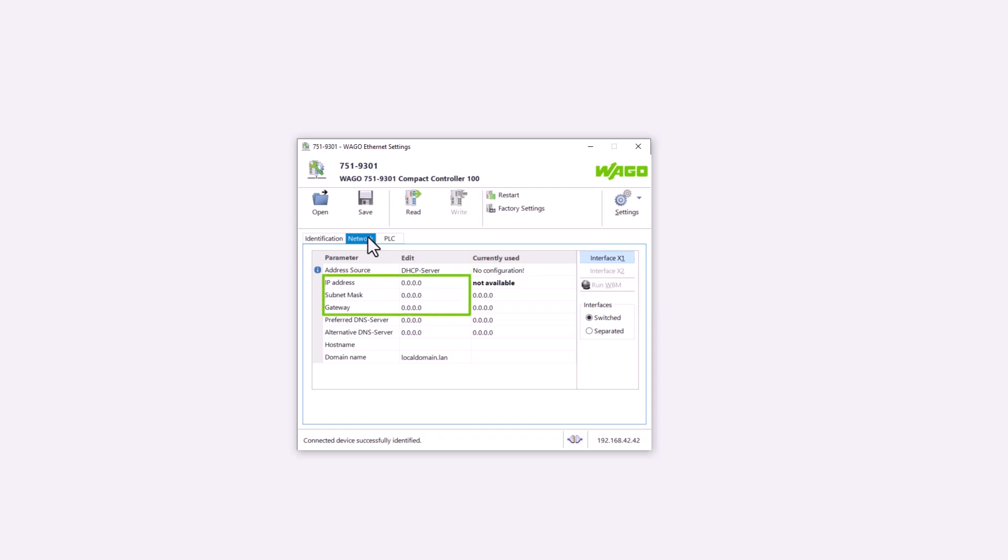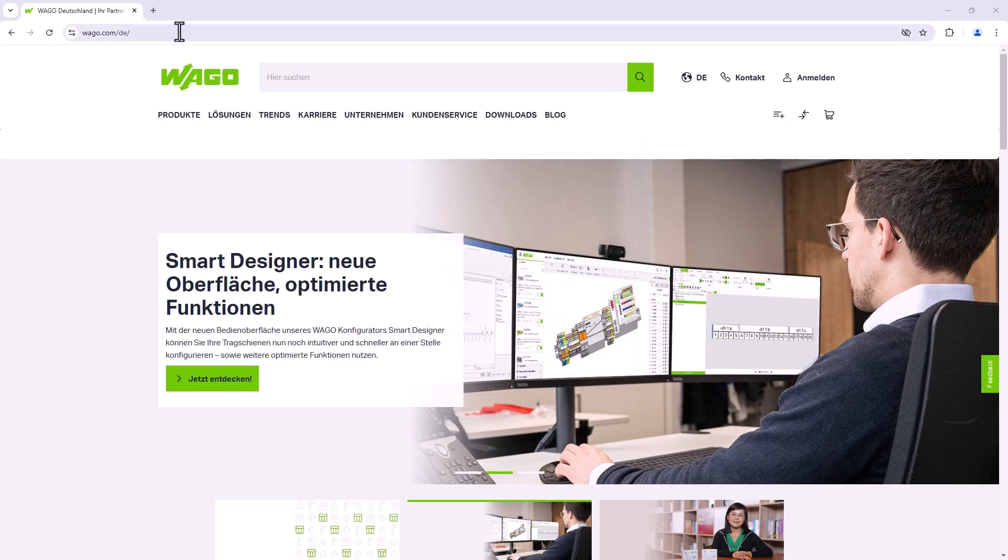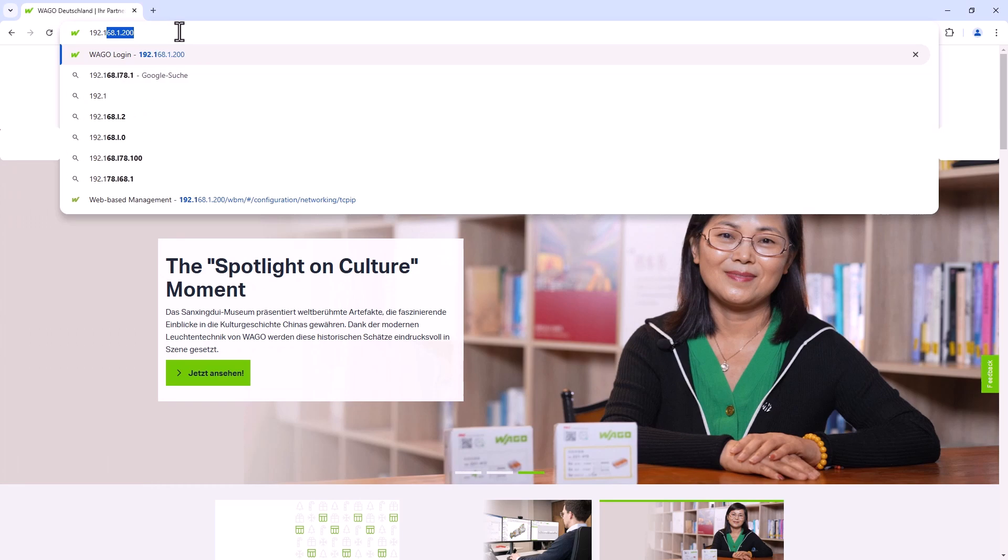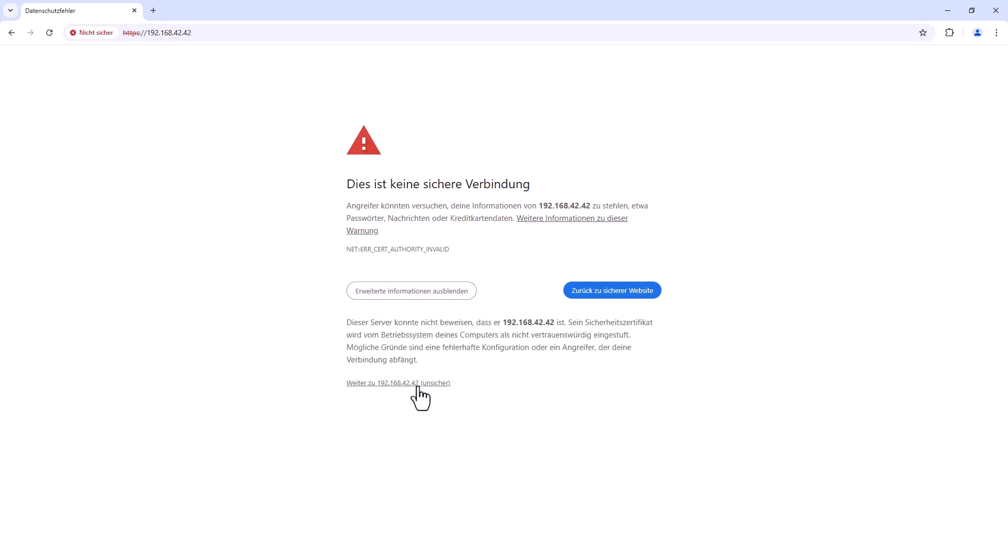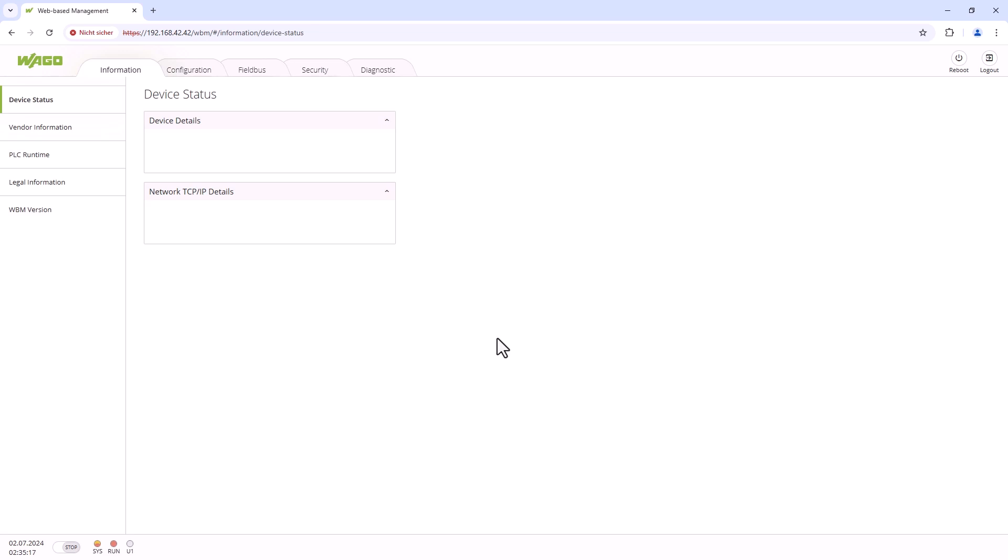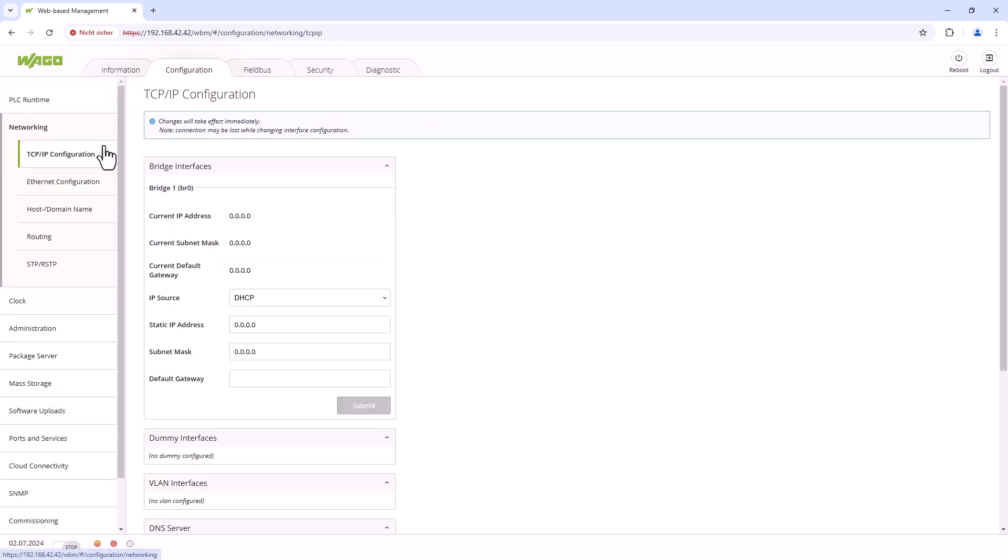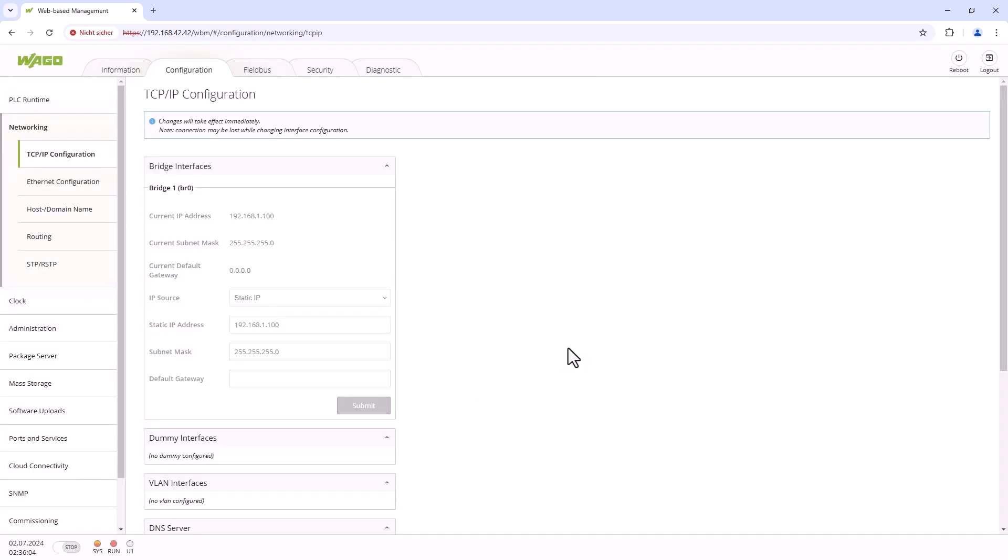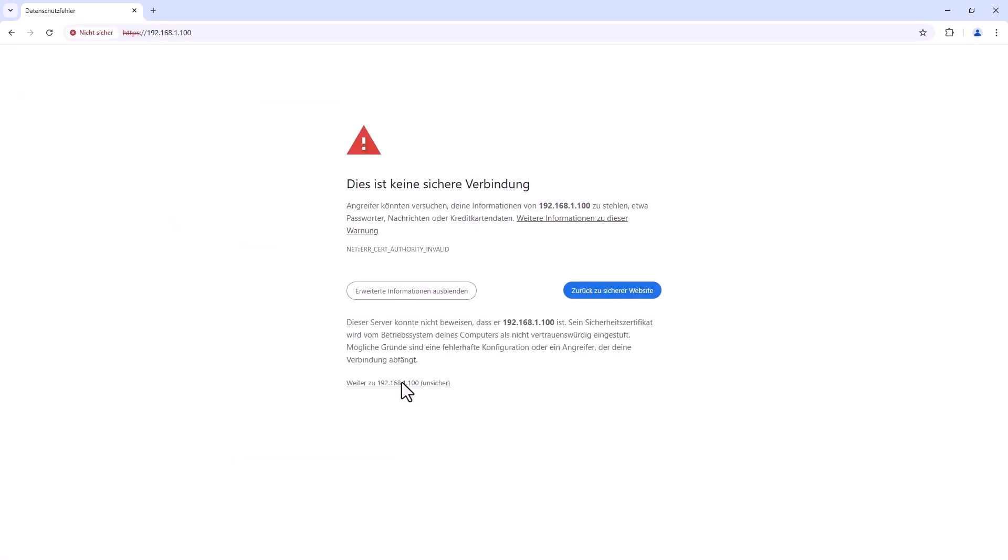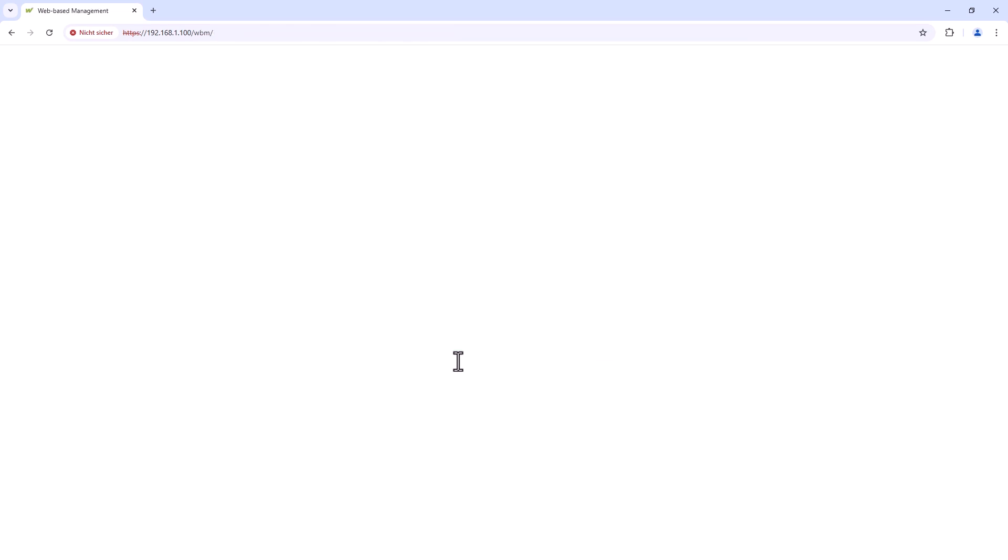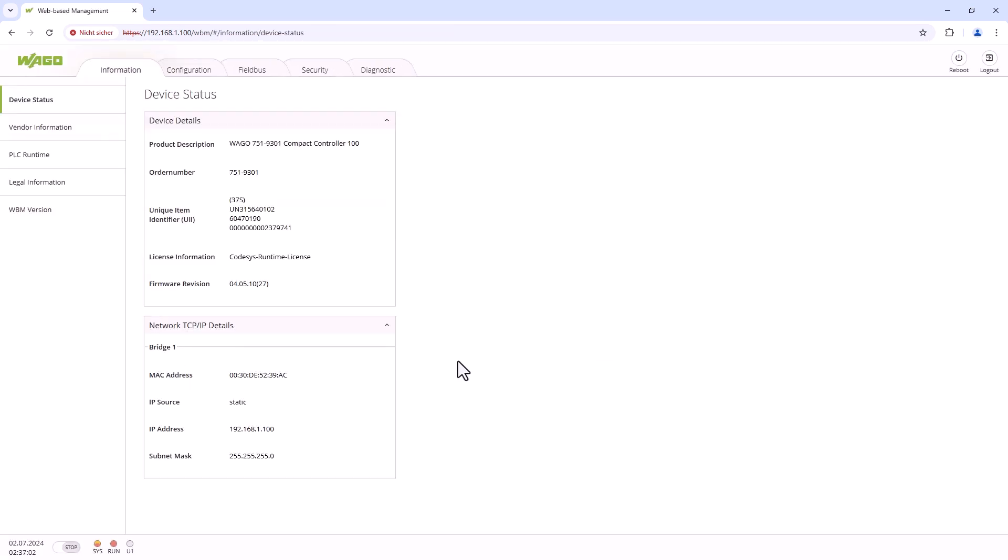However, the USB Ethernet interface also gives us the option of assigning the IP address directly in the web-based management system rather than using the Ethernet settings. To do this, we open the web browser and enter the IP address 192.168.42.42. The web-based management opens and we enter a static IP address for X1. We then enter the newly assigned IP address in the web browser, the WBM reopens, and we are connected. But now not via the USB cable, but via the Ethernet interface of the controller.